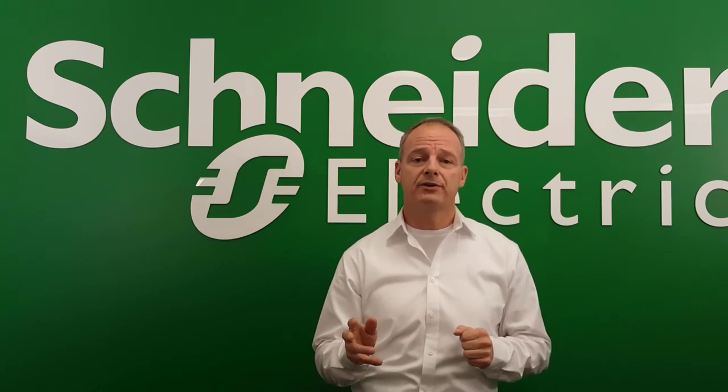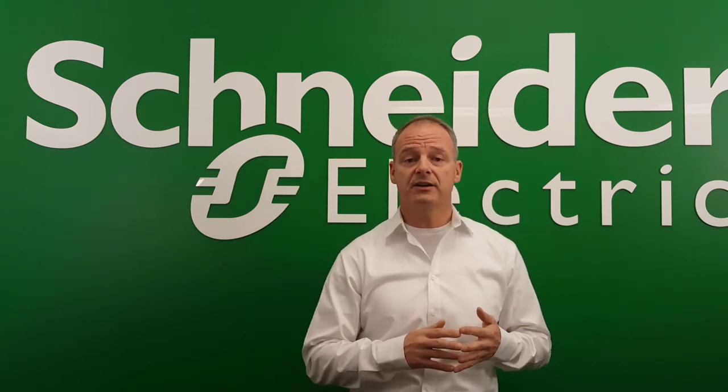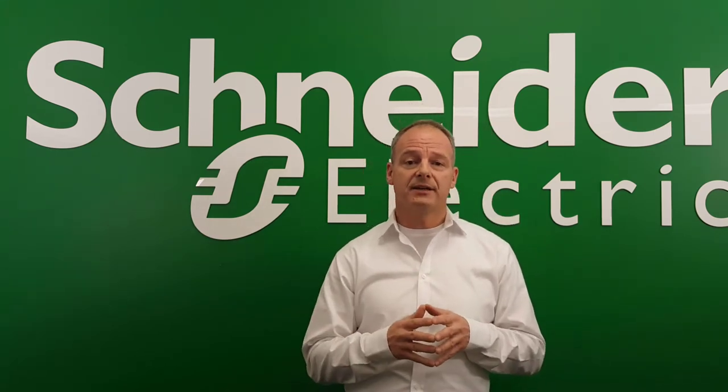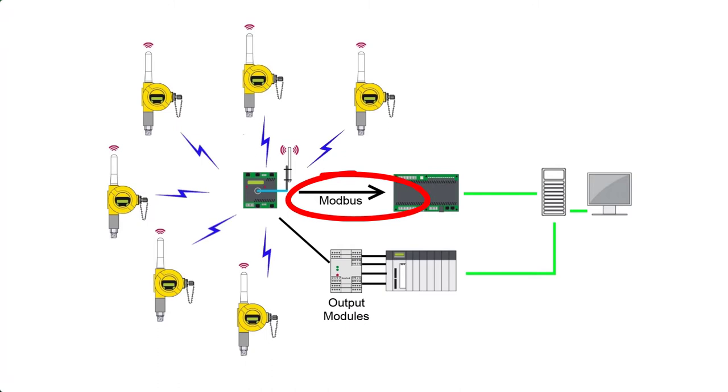From an installation perspective, AccuTech networks can literally be deployed in just a few hours. Configuration is seamless and can be accommodated individually through the integrated LCD screen on each field device, or through a centralized AccuTech Manager software application at the base radio. The networks are designed for long service life. The batteries are specified for at least 3 years and can last a lot longer when using high efficiency configurations. Once deployed, the wireless network can be connected to any RTU, data radio, or directly into a host network. The serial Modbus connection is via RS-485 and is configurable for use with any suitable third party device.